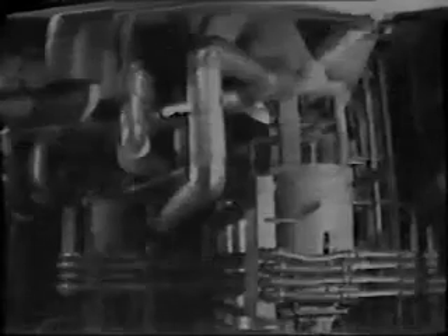When considering protection of the generator, we must not forget the prime mover. For example, suppose an insulation failure occurred to the winding inside this generator. It would not be sufficient just to trip out the main breaker and disconnect the unit from the electrical system. We would also need to trip the stop valves and shut down the prime mover so as to prevent further damage. Similarly, if a problem occurs within the prime mover, which necessitates tripping the unit, intertrips must be provided to trip out the generator breaker as well.